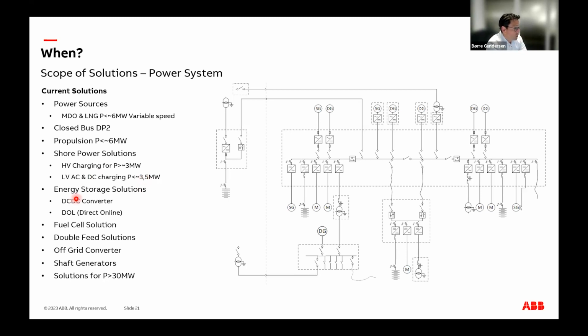And then for energy storage, there are two ways to introduce it on a DC-based system. You can do it through a DC-DC converter, as shown here, which controls the flow of energy in and out of the battery. Or there's what's called direct online, meaning you connect the battery directly to the grid. You can do that, but then controllability is less, though equipment is less and efficiency is higher. So the bigger battery you have on board, the more sense it makes.